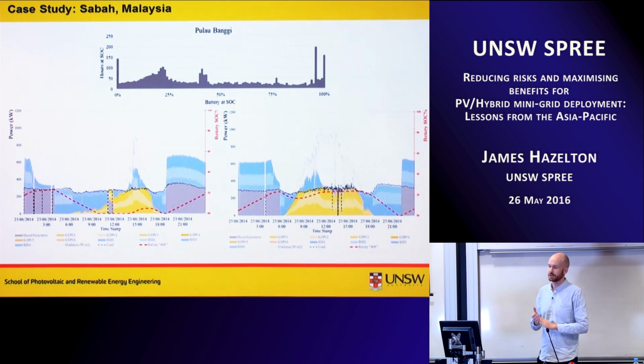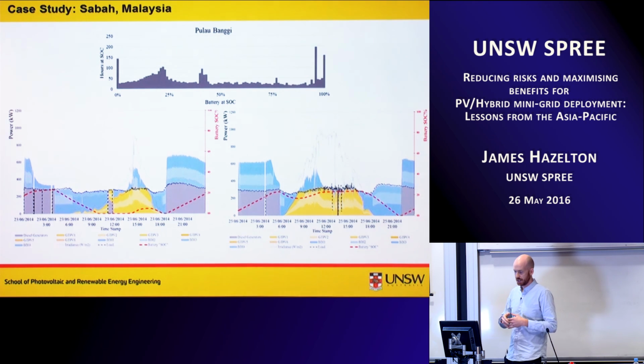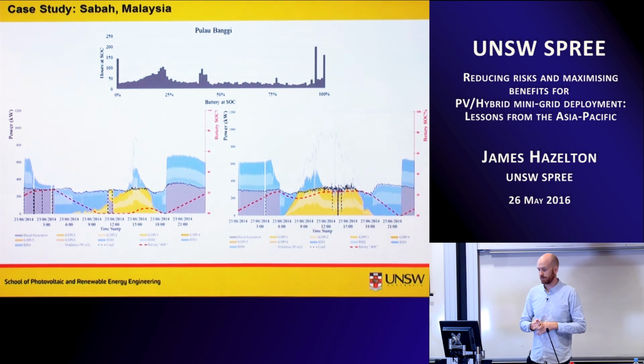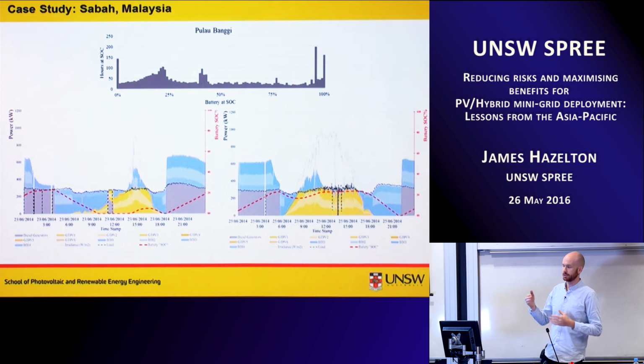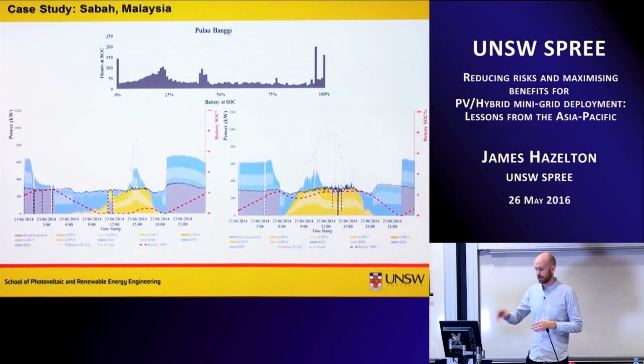The battery state of charge wasn't accurately reflecting the actual battery state of charge. The way we identified that it was an issue with the data signal rather than the actual battery state of charge was that, if you look at the chart on the right, we could produce a lot more solar than what's being generated, but this curve is quite reflective of a float charge in sealed lead acid batteries, where the voltage stays the same but current gradually diminishes as the batteries fill up. So I'm pretty confident this battery state of charge indicator is wrong.